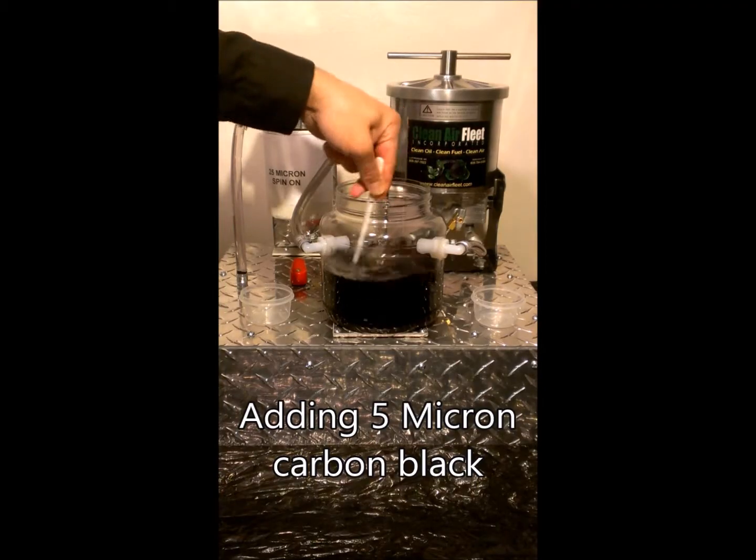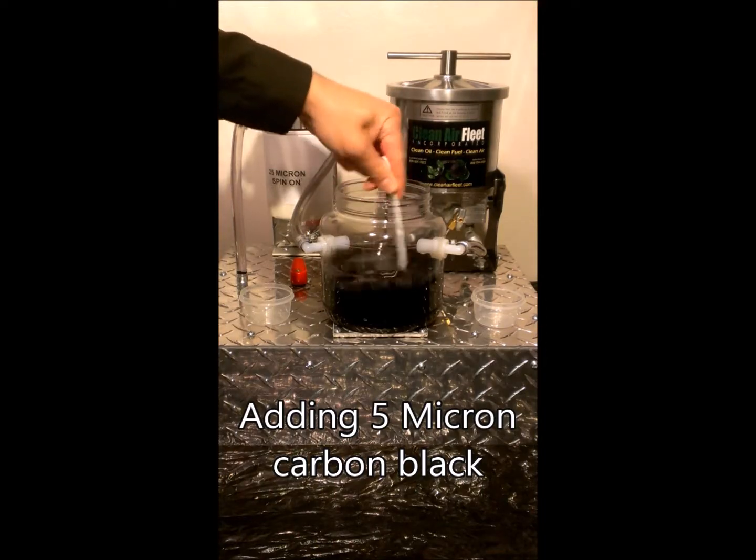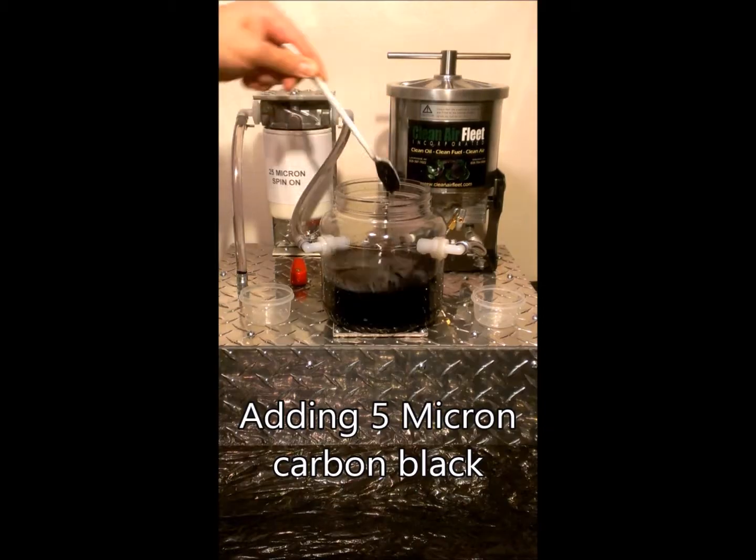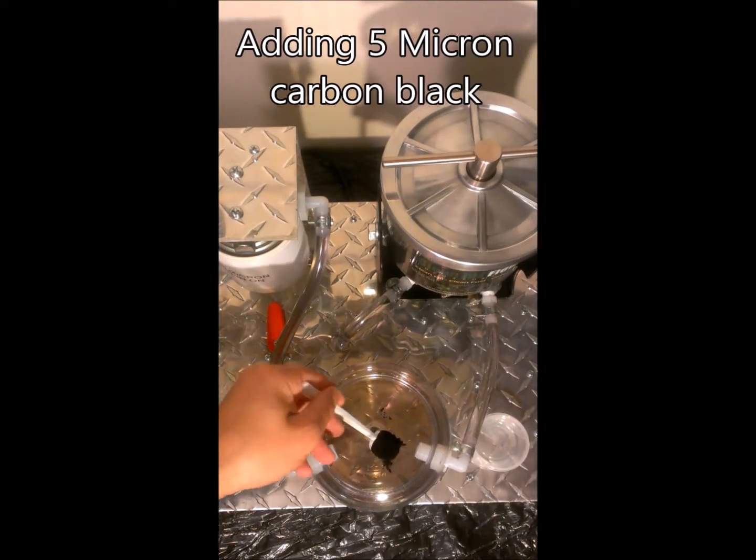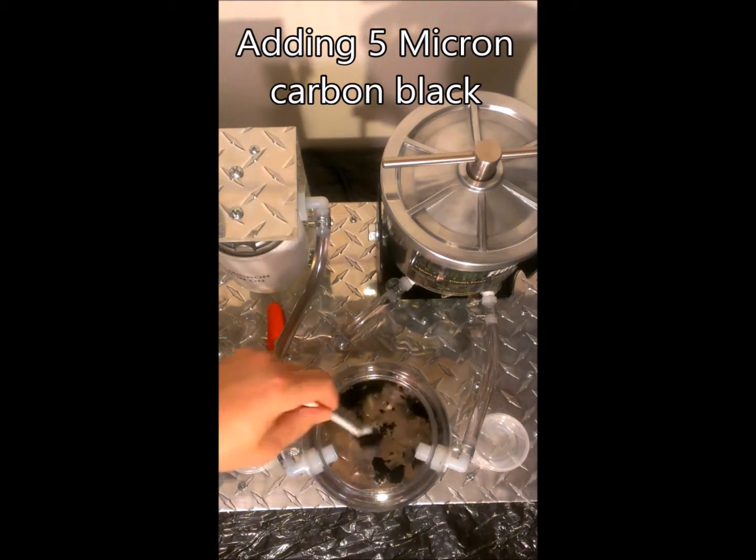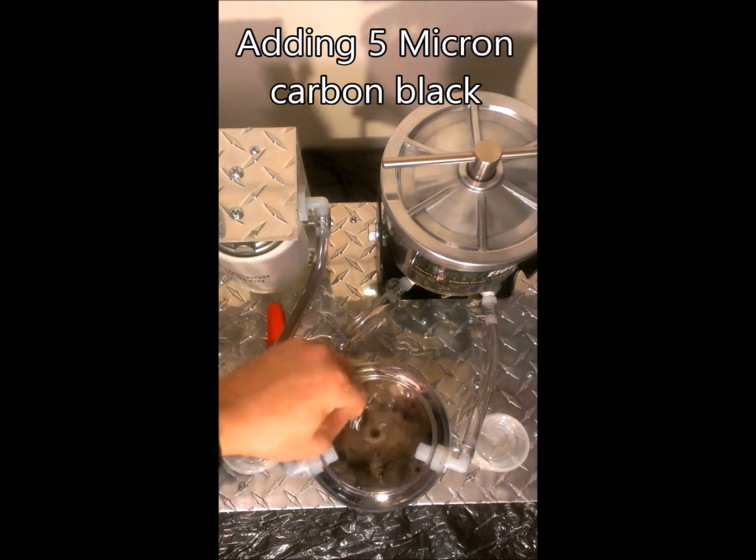A standard spin-on filter will not remove the particles smaller than 25 micron in size. From the top view adding the carbon, you can see how quickly the fine powder mixes into solution, turning the oil completely dark.